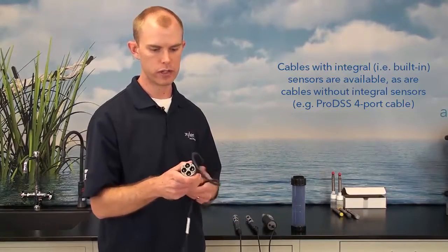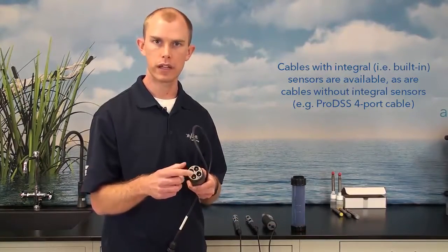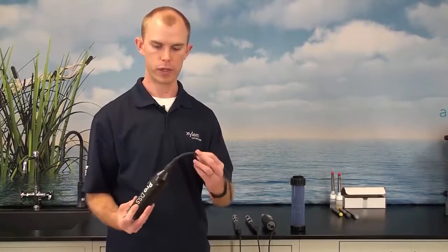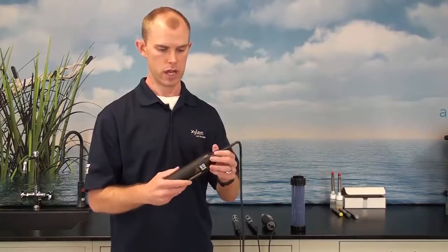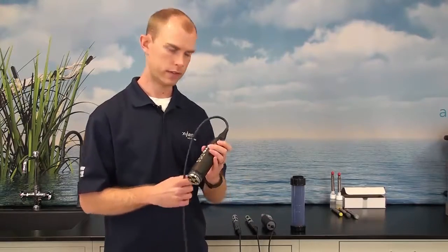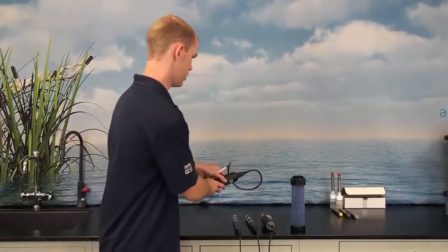With this cable you can plug in or connect any ProDSS sensor into any sensor port, because these sensor ports are universal. This ProDSS 4-port cable also comes with an optional depth sensor mounted up here. If there is no depth sensor, then this little portion at the top will not be part of the cable assembly. These cable assemblies are available in up to 100-meter lengths. So this is the ProDSS 4-port cable.